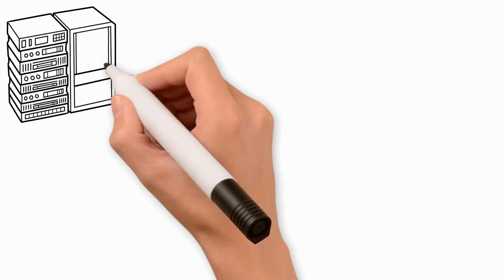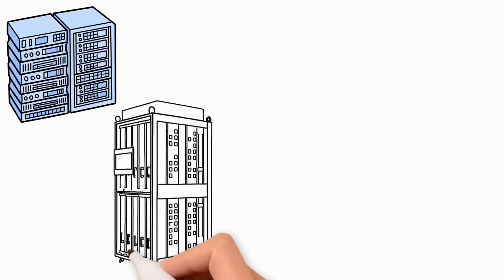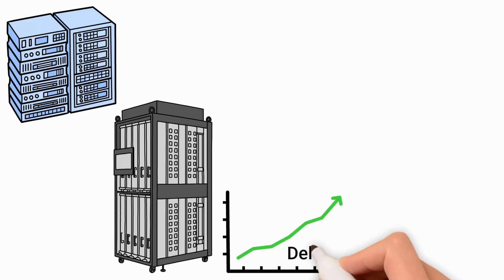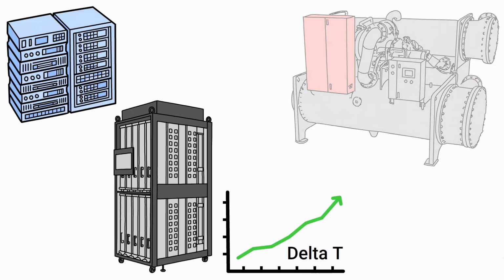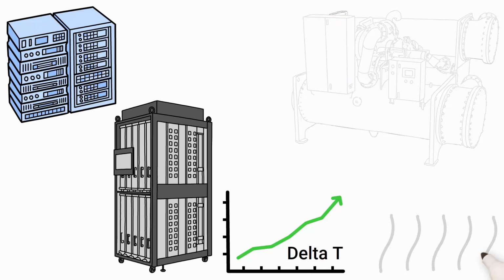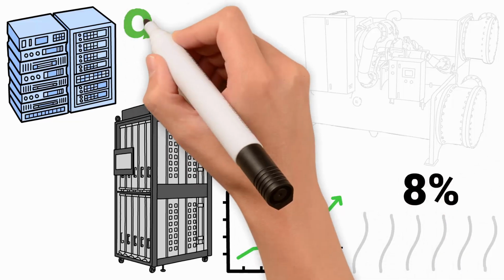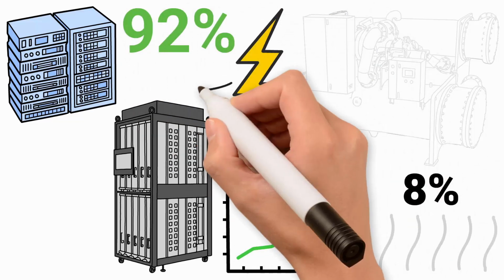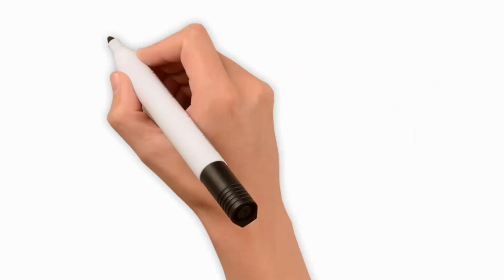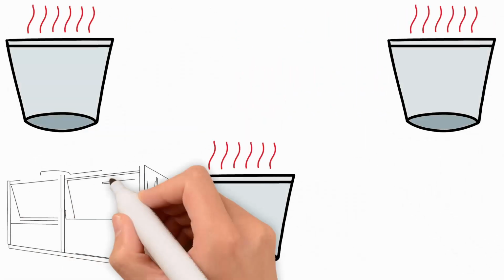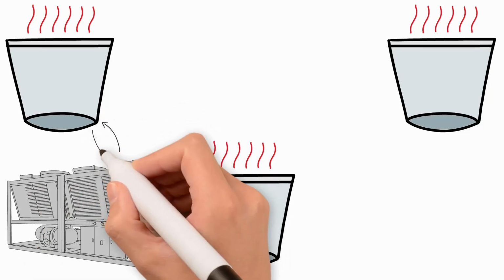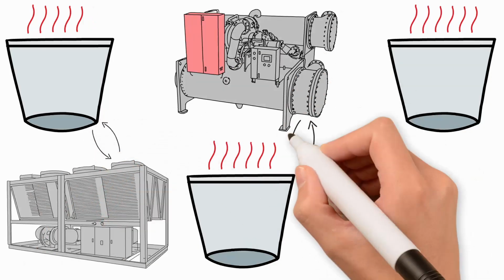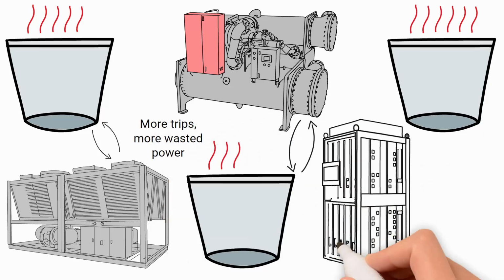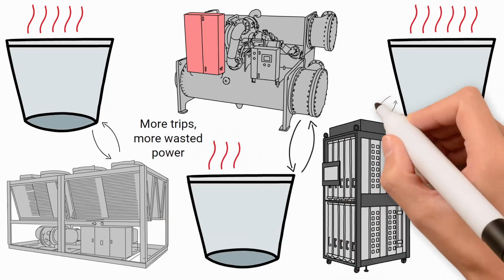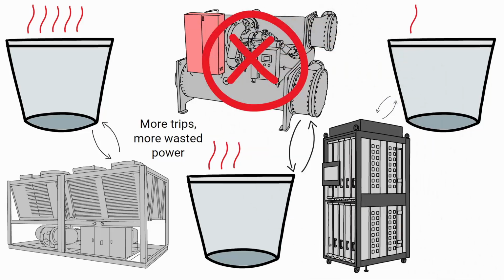Now the third, it uses liquid rack spray cooling. By operating at a much higher delta T, compressors are eliminated entirely. Cooling overhead drops to as little as 8%. That means up to 92% of your capacity now goes to compute. Think of it like carrying buckets of heat. With traditional systems, each trip only removes a little, so you need compressors to finish the job. With liquid rack, each bucket carries much more heat per pass. No compressors required. Fewer trips, less wasted power.